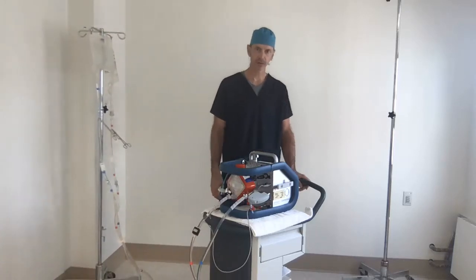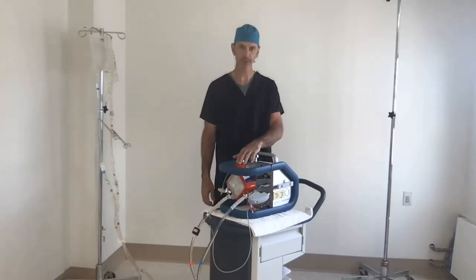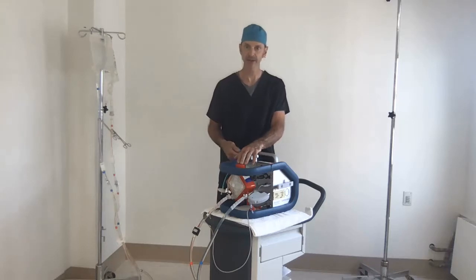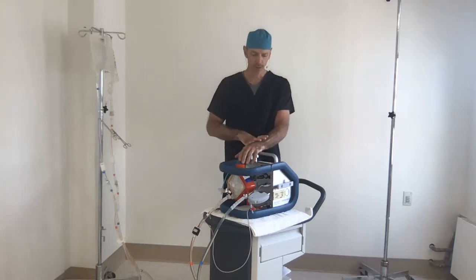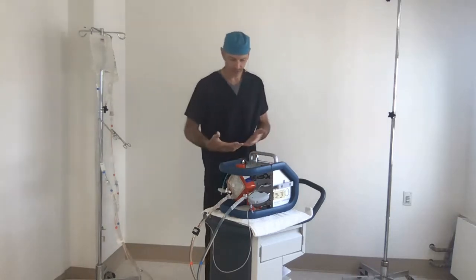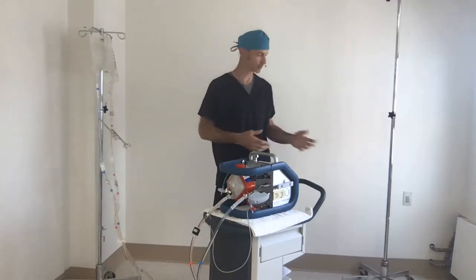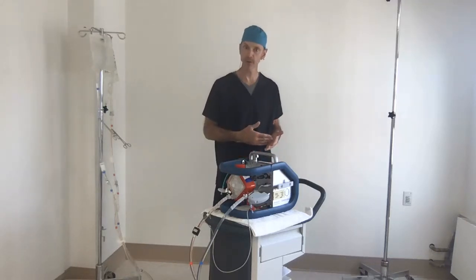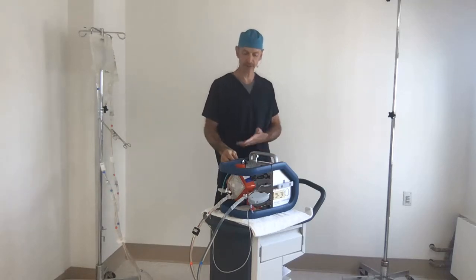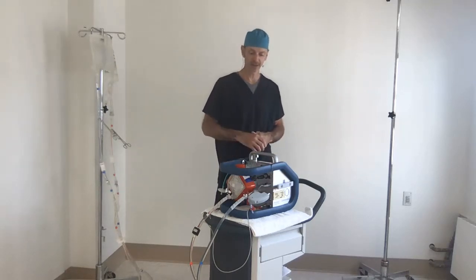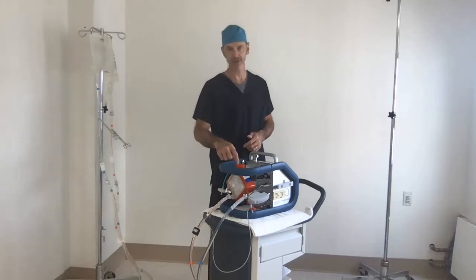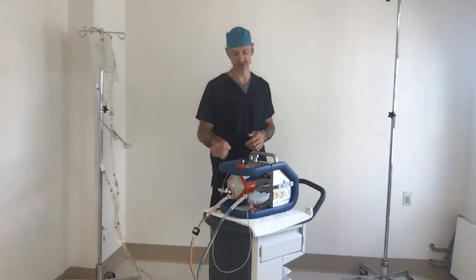So let's walk through how we train for jump the pump and console change, hand cranking on a Cardiohelp system. When I'm the instructor, there's a learner, and they are doing whatever they're doing around the room, and when we reach that point in the competency where I need to test these skills, then I need to cause this pump to fail. And the easiest way to cause the pump to fail is to disengage it. The easiest and fastest is just disengage it from the motor.